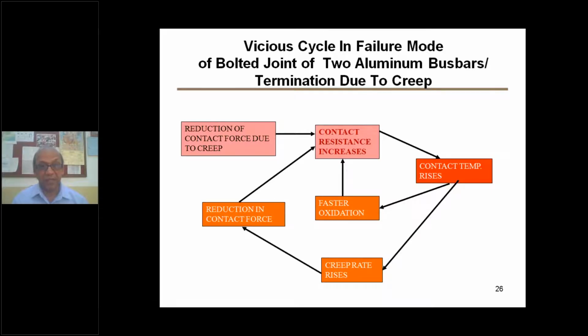When contact temperature rises, two things happen: faster oxidation due to higher temperature, and the creep rate also rises, causing further loosening of the conductor. So there is reduction in contact force, further reduction in contact force, and contact resistance increases further. This cycle may continue for 10 days, a month, three months, or even a year, and then it converts into a failure.